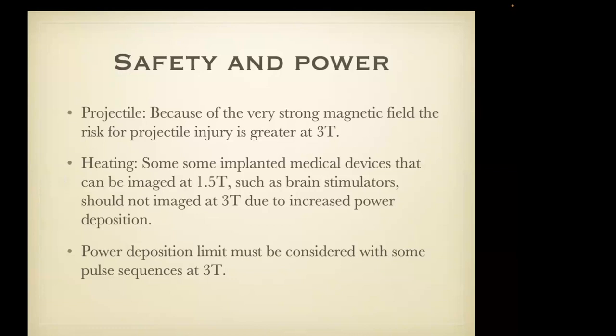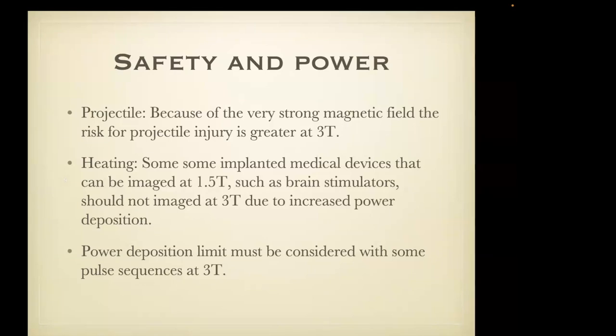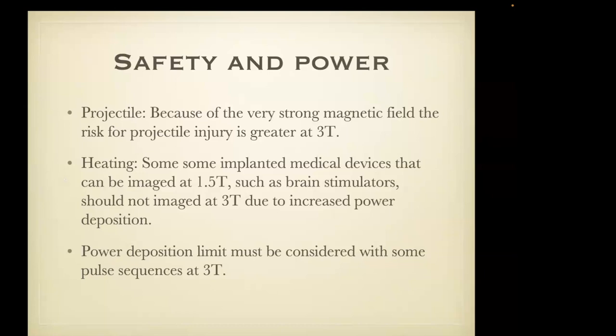The other issue, which is much more commonplace and in a sense occurs in every patient, is the heating that occurs at 3 Tesla. Some medical devices that you would consider safe to image at 1.5 Tesla — such as implanted brain stimulators — are recommended not to be imaged at 3 Tesla because of increased power deposition. So as you design pulse sequences at 3 Tesla, you must consider power deposition because it's going to be greater.